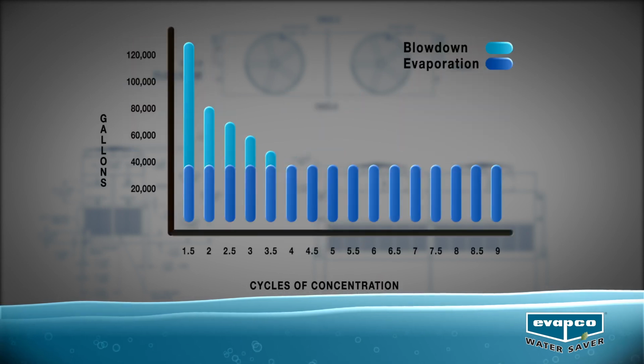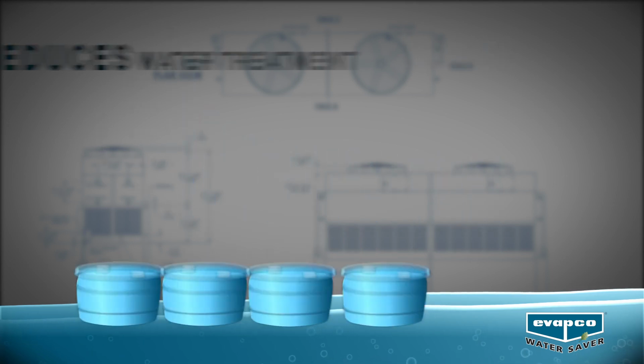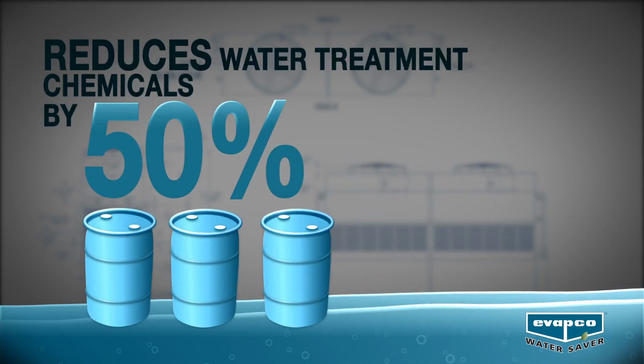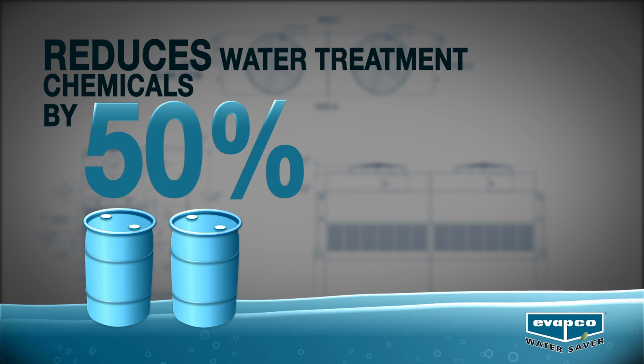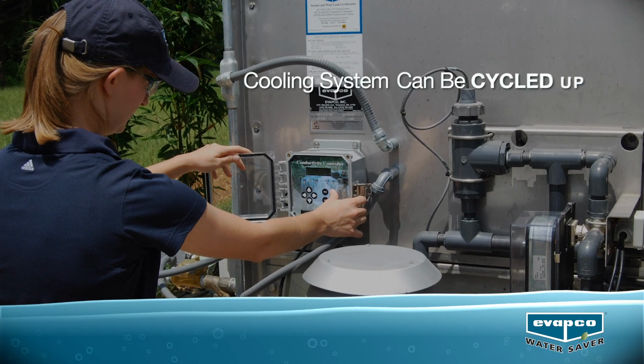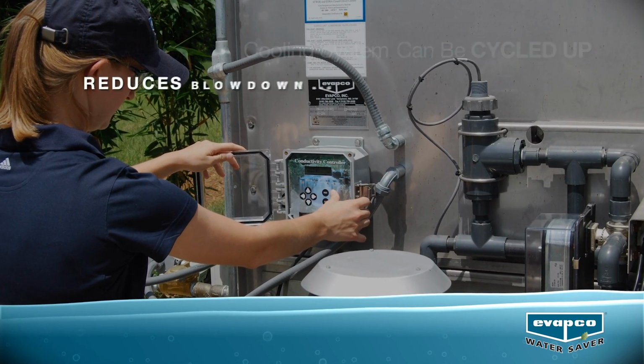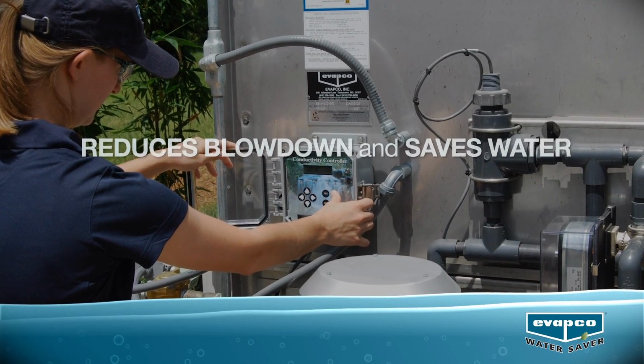The higher cycles of concentration achieved with this innovative design also reduces the amount of water treatment chemicals needed by 50%, providing additional operating expense savings and positive environmental impact. The beauty of the EVAPCO Water Saver technology is that it proportionally reduces the dissolved ions, which have historically limited operating cycles of concentration in evaporatively cooled systems. This allows the cooling system to be safely cycled up to reduce blowdown and save water.